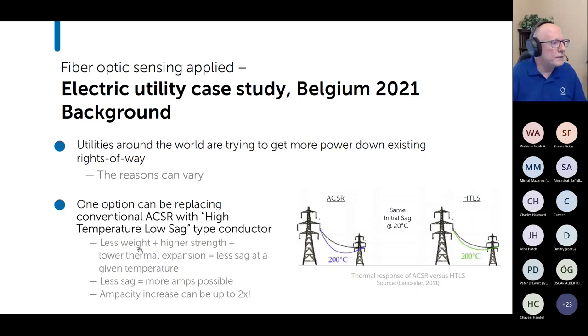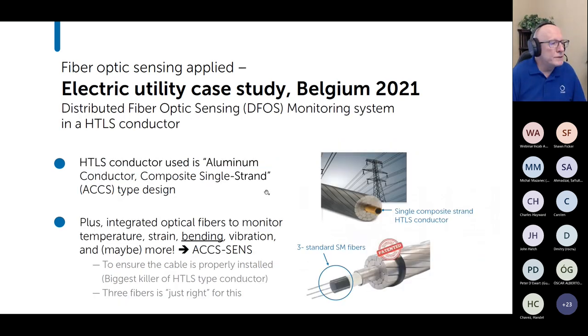And again, just as background, of course, with the high temperature, low sag conductors, what you're doing is lowering weight, getting higher strength and lower thermal expansion. And so what that means is you get less sag at a given temperature than a traditional cable. So the sag at 200 degrees C on ACSR might be this much, but with the HTLS cable, it might be a lot less, on the order of maybe half. And less sag means more amps. And that ampacity increase can be as much as a factor of 2. So that's why more and more you see utilities adopting various specific designs that are high temperature, low sag type conductors. But like most things in life, there is a trade-off.